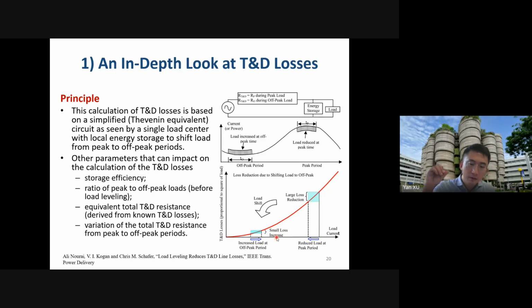So you can see that when the current is higher, the power loss increases quadratically rather than linearly. The principle is that if we reduce the load during the high current peak period, and shift this load to the low current off-peak period, we will see a gap between the loss corresponding to each period. This loss, directly speaking, equals I squared peak R minus I squared off-peak R. So although the x-axis currents are the same, the y-axis values are different, because this is a quadratic curve. I hope you can understand my point.